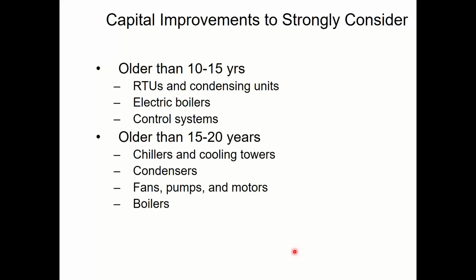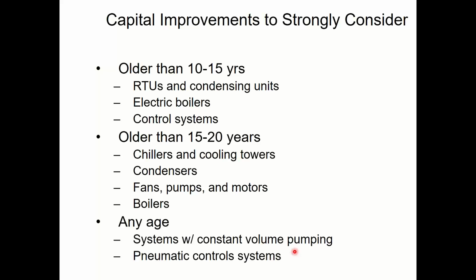That next range of stuff, that 15 to 20 years, chillers I'm looking at in that range, cooling towers, the fans in my indoor air handlers, my boilers. Now, I just told you boilers sometimes last 30, 35, 40 years, but maybe around 15 or 20 years, I'm looking at a boiler that was 78% efficient, and now I can replace it with one that's 95% efficient. Just from an efficiency standpoint, I may pull the trigger on that project. So these are the kind of ages on when I want you to think about you should replace it instead of repairing it, if you will.